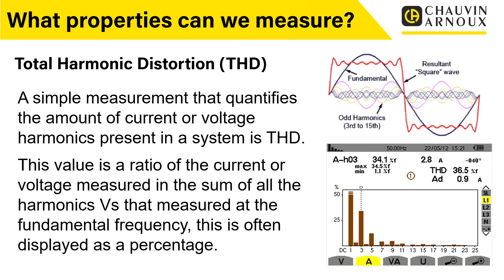But this is a very useful measurement, THD. It's a quick measurement. You take the THD, and then obviously if you looked at it and said, oh God, we've got a lot of harmonics present here, that's when you'd start to do the Fourier analysis. You'd start to look into it in more detail. Right, where are they coming from? What are they? Why have we got them? What's the effect? So THD is almost your sort of starting point measurement. If your THD is okay, you really know you haven't got a harmonic problem. Whereas if your THD is high, then obviously you would start to go into that a lot more and start to dive into it. So THD is almost the starting point for harmonic analysis, and then you would really start to diagnose into that using the waveforms and things like that afterwards.